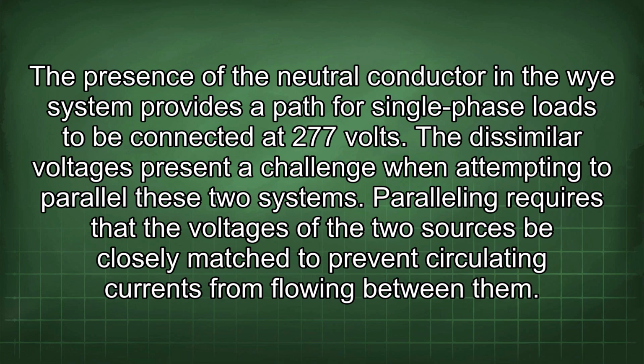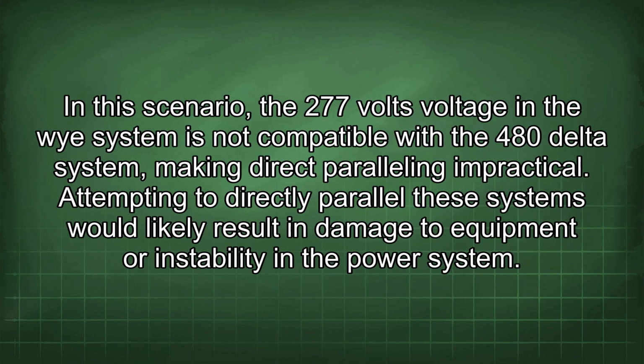The presence of the neutral conductor in the Y system provides a path for single-phase loads to be connected at 277 volts. The dissimilar voltages present a challenge when attempting to parallel these two systems. Paralleling requires that the voltages of the two sources be closely matched to prevent circulating currents from flowing between them. In this scenario, the 277 volts in the Y system is not compatible with the 480 delta system, making direct paralleling impractical.